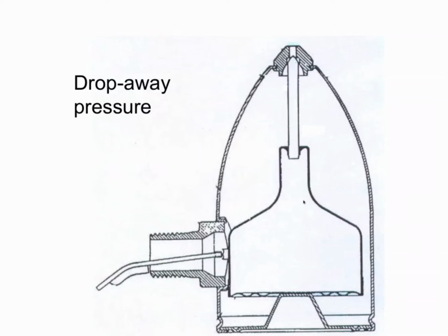So drop away pressure works like this. Let's say you're starting up and you got steam pressure. Like, so you get to 2 psi or 5 psi, whatever you're running. And you're pushing with relatively low pressure against a big wide bottom. And that is shutting the vent. Now that's being opposed by atmospheric pressure that's trying to fit in through this little hole. So it's kind of like when...